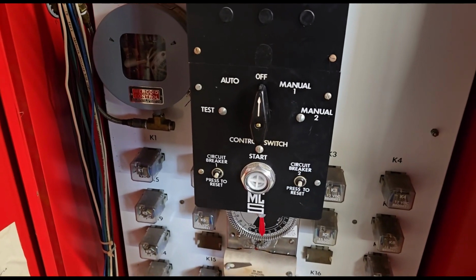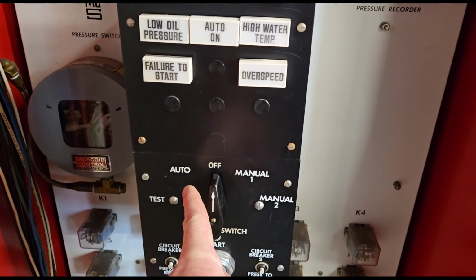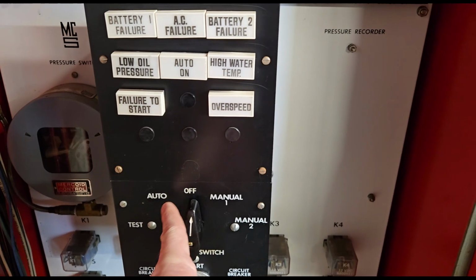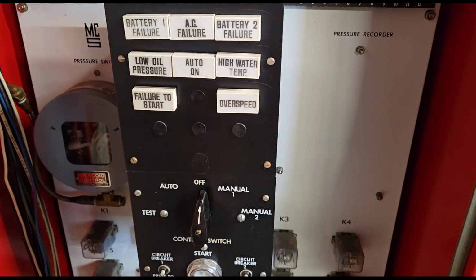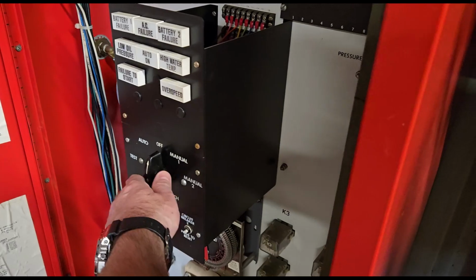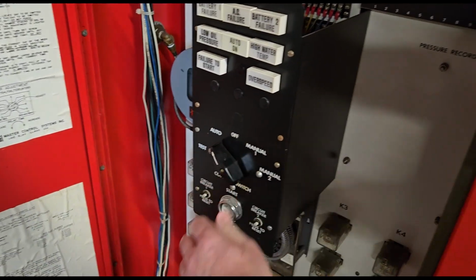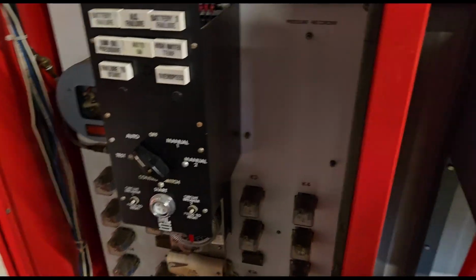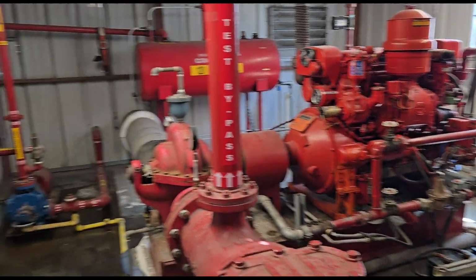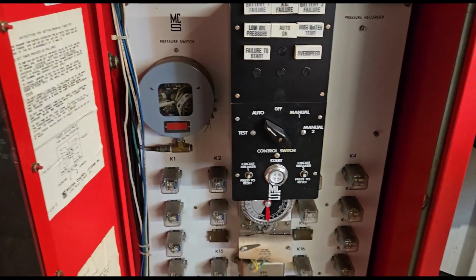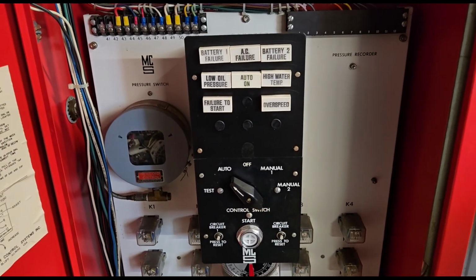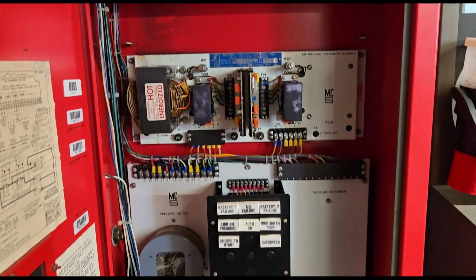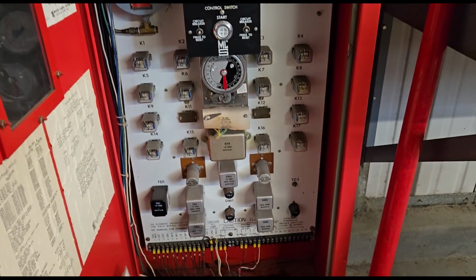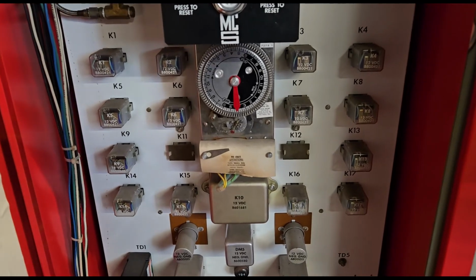So we have our gauge, and originally it was on auto. We had it off for testing, so we're just going to put it back to auto, and that way the pump will be back on. So I'm going to stand to the side. Going to turn it to auto, just like that. And nothing turned on, so that's a good sign. So back on auto. Going to show the controller inside one more time. It's an older style controller for sure. Look at all these little switches in here. It's crazy.